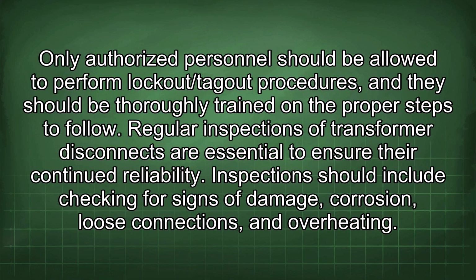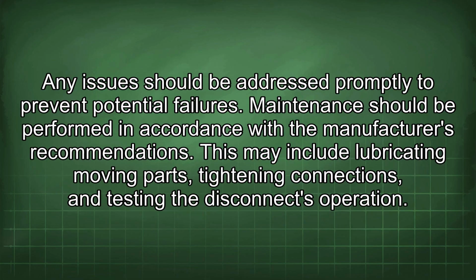Only authorized personnel should be allowed to perform lockout/tagout procedures, and they should be thoroughly trained on the proper steps to follow. Regular inspections of transformer disconnects are essential to ensure their continued reliability. Inspections should include checking for signs of damage, corrosion, loose connections, and overheating. Any issue should be addressed promptly to prevent potential failures. Maintenance should be performed in accordance with the manufacturer's recommendations. This may include lubricating moving parts, tightening connections, and testing the disconnect's operation.